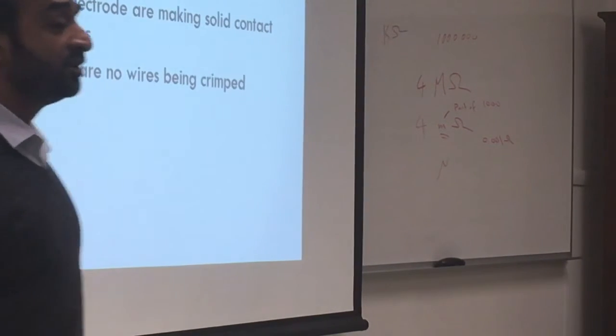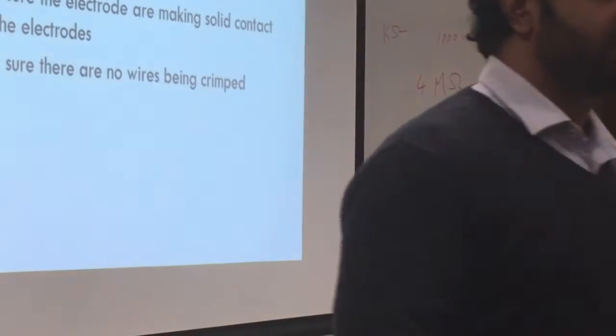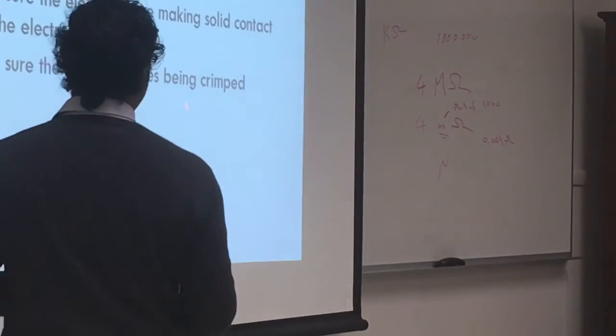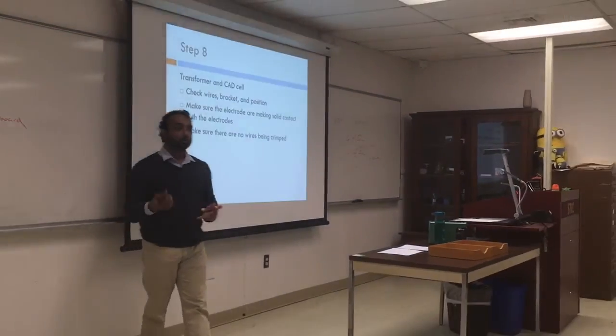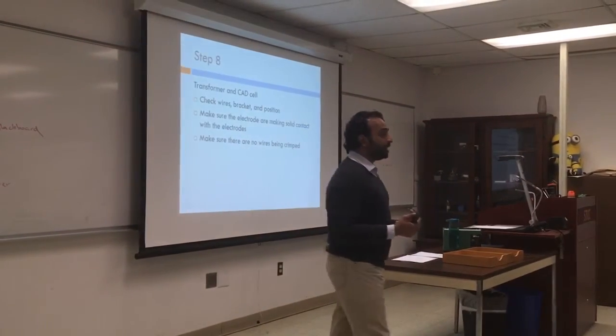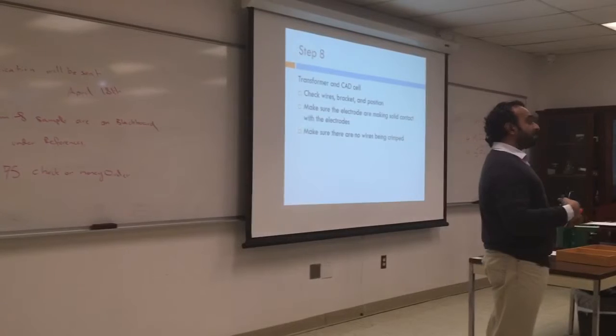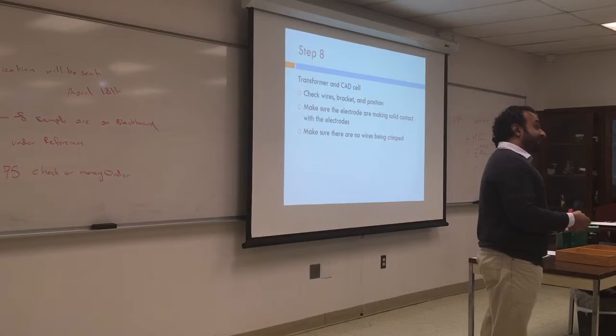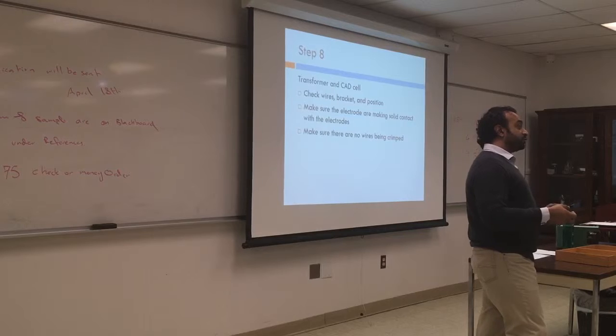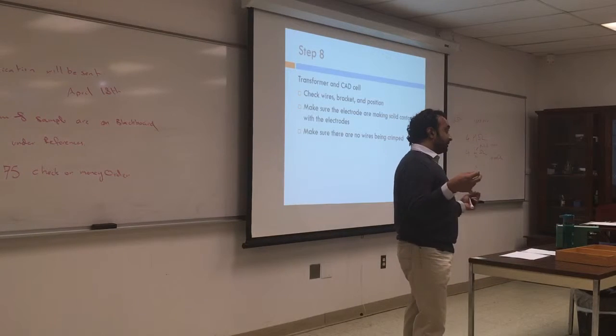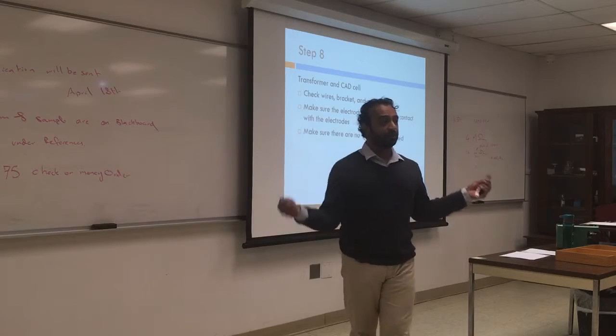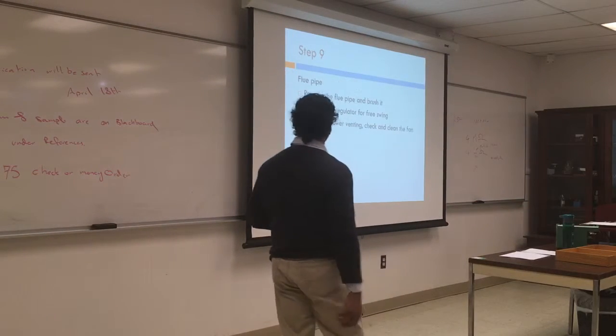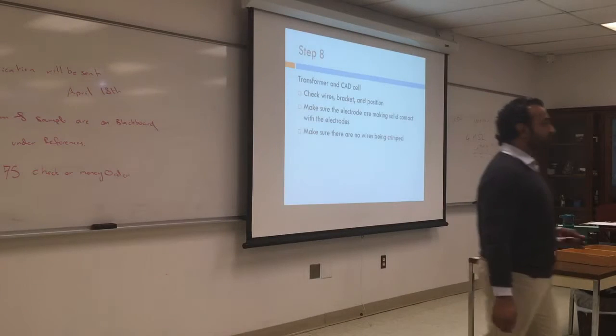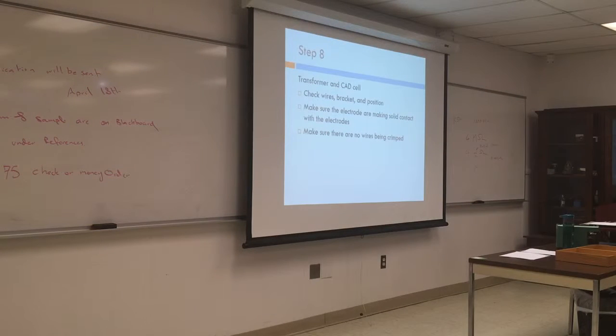So check wire resistance, and make sure that the electrodes are making solid contact. This happens a lot where the bus bars are not really solid and the springs are not touching completely. Make sure that there are no wires being crimped. This happens a lot. You try to force the transformer in place and one wire gets crimped, and sometimes when you crimp them, you cut the wire inside even though the insulation is sound, and that's very frustrating because the wire will look complete and continuous. However, if you run the ohms through it, it's not continuous. Alright, how would you know if the electrodes are not making a solid connection? It will not ignite.